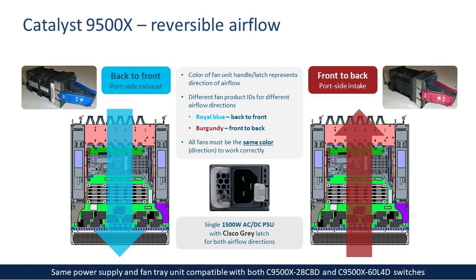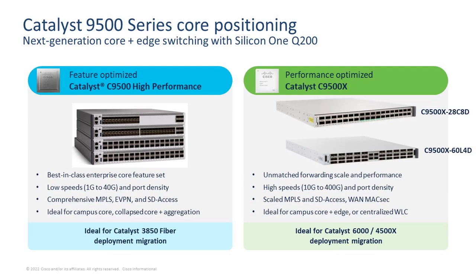This design avoids the need to increase fan tray RPM or add more fan trays to cool the system. The 9500X-60L4D uses the same power supply unit and fan tray unit as the 28C8D model released early last year. This means we get all the airflow benefits of that fan tray, including reversible airflow — supporting both front-to-back and back-to-front depending on your rack space requirements. There are two separate PIDs for the fan trays, one for back-to-front and one for front-to-back. All six fan trays must match in airflow direction — you cannot mix and match.